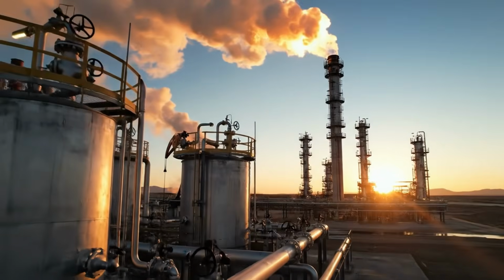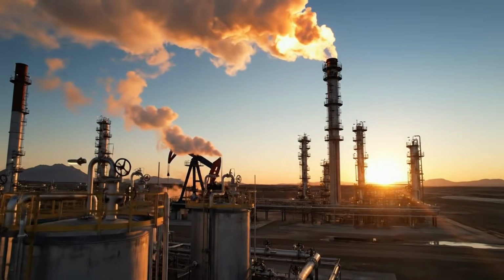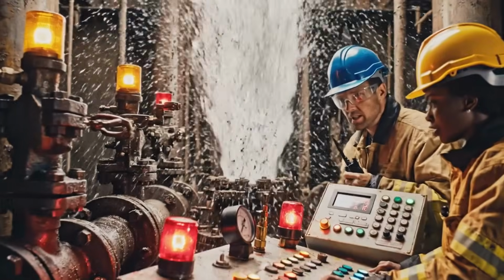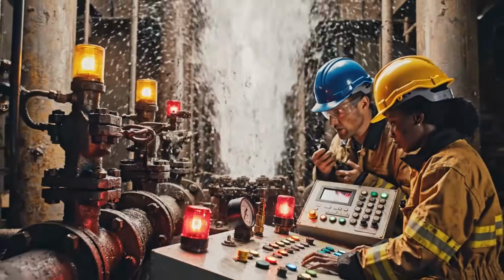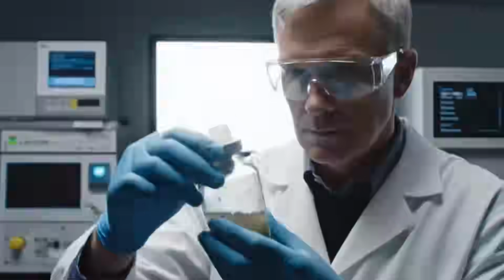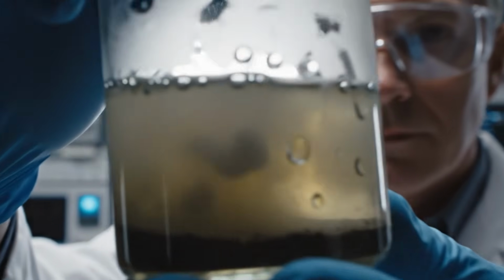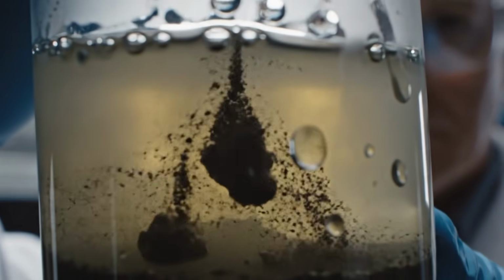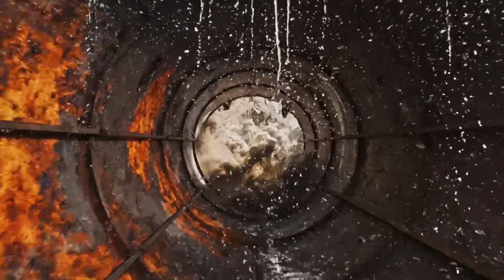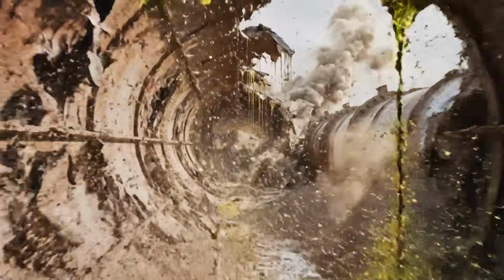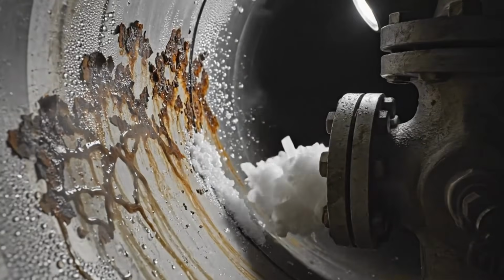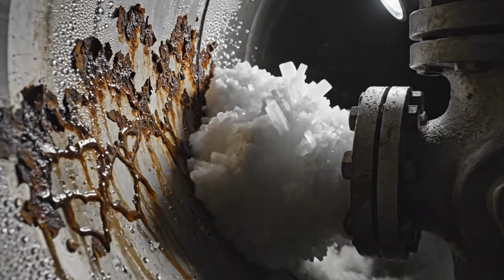The first step consists of primary separation. For this, pressure vessels designed to divide the mixture according to density and physical behavior are used. In three-phase separators, the incoming flow reduces its speed and organizes into three streams. Water accumulates at the bottom. An intermediate layer holds condensates or associated liquids, similar to light hydrocarbons. The gaseous phase concentrates in the upper zone. This process seems simple, but it requires fine control of pressure, temperature, and internal level to function without losses.